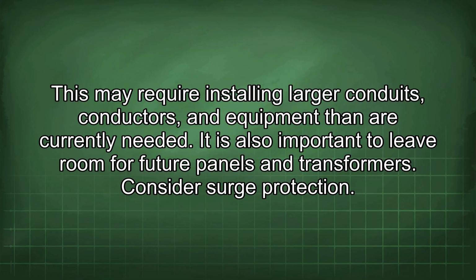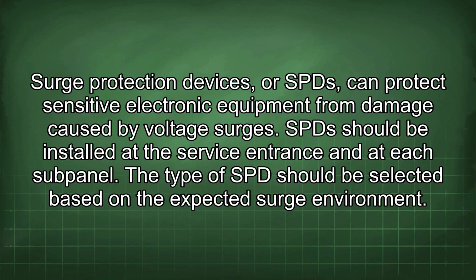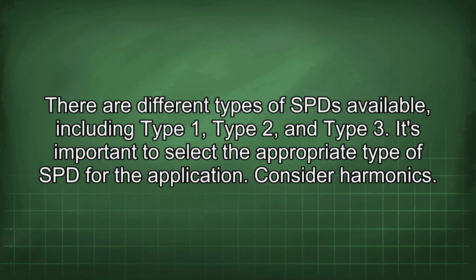Consider surge protection. Surge protection devices, or SPDs, can protect sensitive electronic equipment from damage caused by voltage surges. SPDs should be installed at the service entrance and at each subpanel. The type of SPD should be selected based on the expected surge environment. There are different types of SPD available, including Type 1, Type 2, and Type 3. It's important to select the appropriate type of SPD for the application.